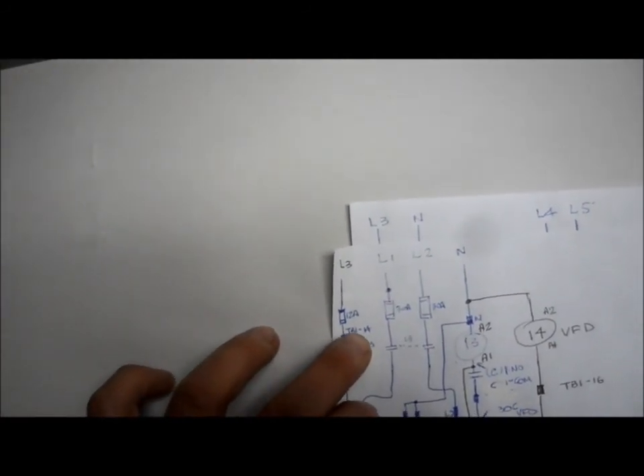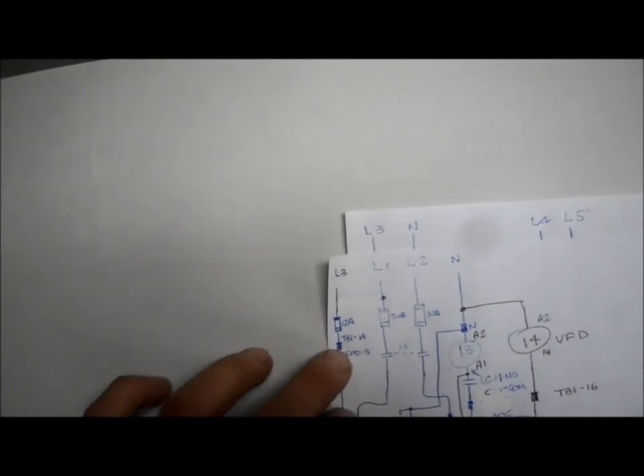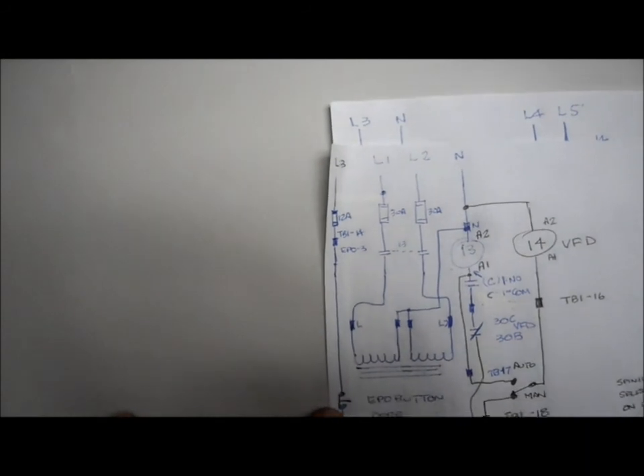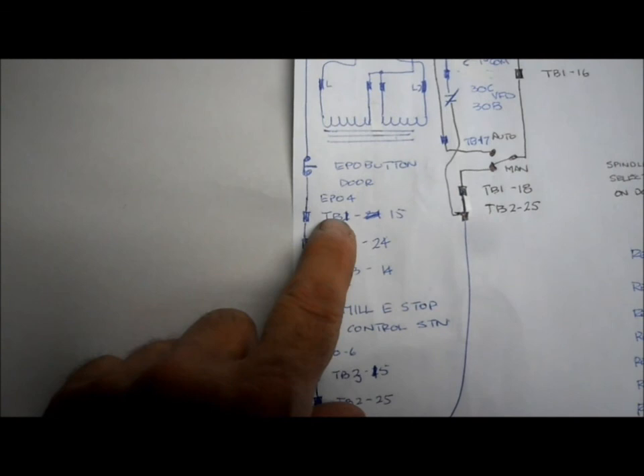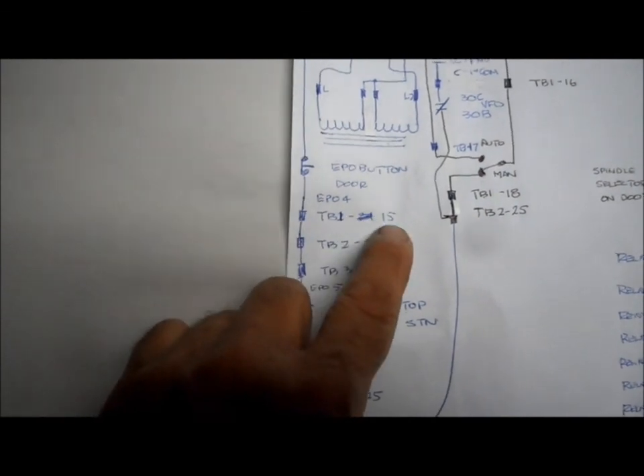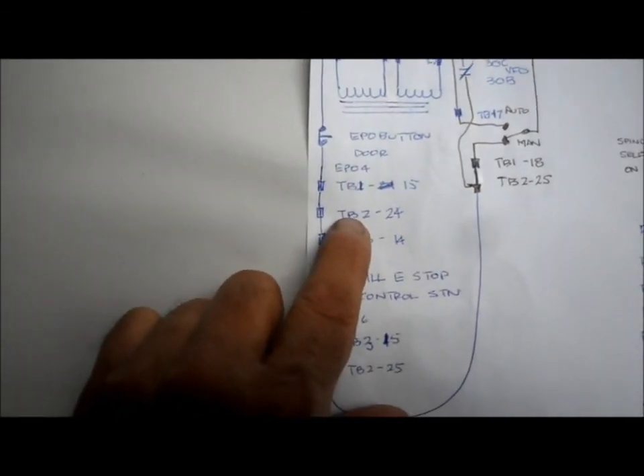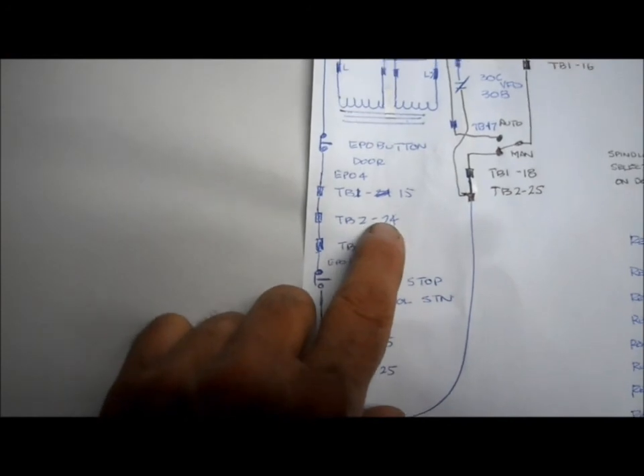And where it starts, it comes from the control fuse, works its way down to terminal block number four, terminal block one, TB1, terminal 14. Every time you see this symbol, that's what it means. Now it's part of the EPO string and it's going to go down. It goes to the EPO button mounted on the door, goes down to terminal block one and terminal 15.